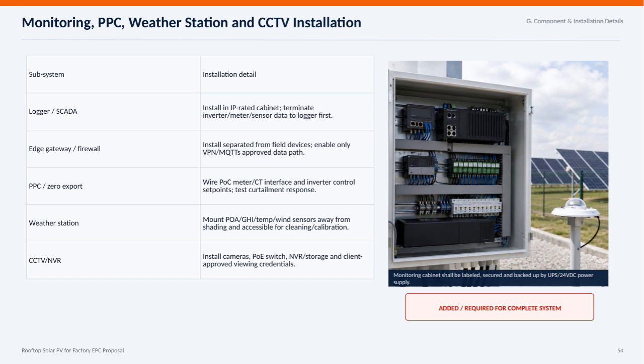For the PPC or zero export functionality, we wire the point of connection meter and current transformer interfaces along with inverter control setpoints, then conduct tests to ensure proper curtailment response. The weather station sensors, including plane of array, global horizontal irradiance, temperature, and wind, are mounted away from shade and positioned for easy cleaning and calibration. CCTV components like cameras, PoE switch, and recording equipment are installed with client-approved access for monitoring. Finally, the entire monitoring cabinet is clearly labeled, securely enclosed, and supported by uninterrupted power supply with UPS and 24-volt DC backup. These additions are essential for delivering a complete, reliable system.